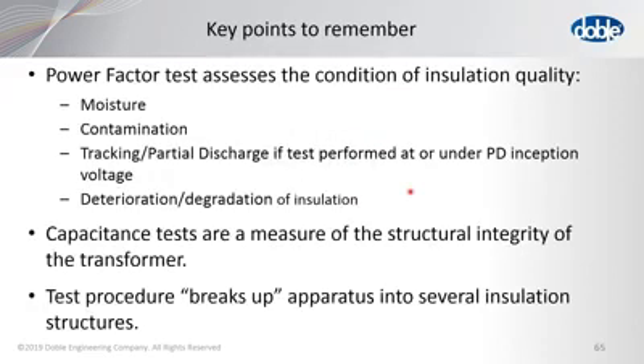In summary, the power factor test assesses the condition of the insulation quality. Those list of 4 things can cause higher power factors and indicate a problem. Now, the capacitance tests are a measure of the structural integrity of the transformer. When you compare to a previous test and the capacitance has changed significantly, we usually say significant is over 5 or definitely over 10%, it shows a structural integrity issue, and it could indicate that a winding has moved.